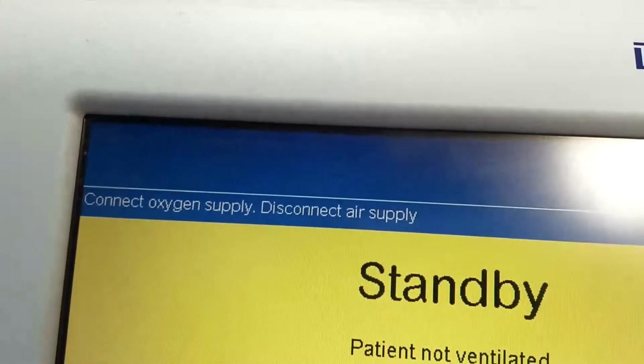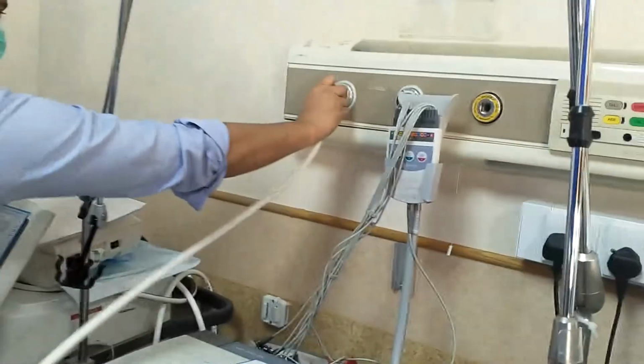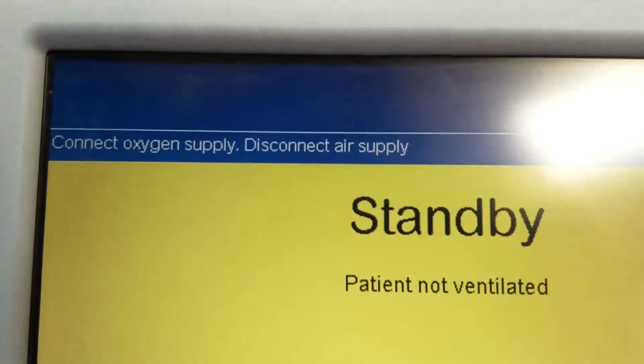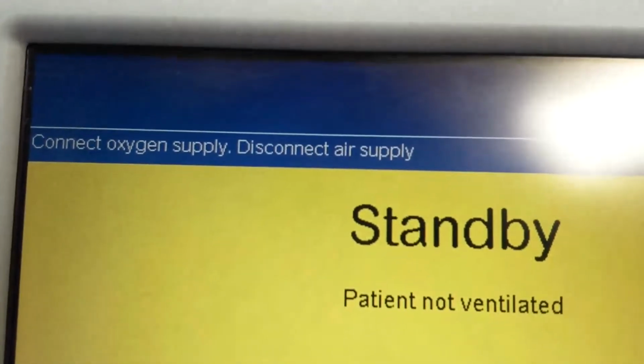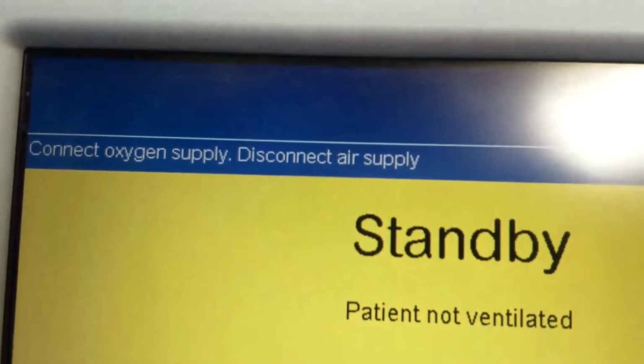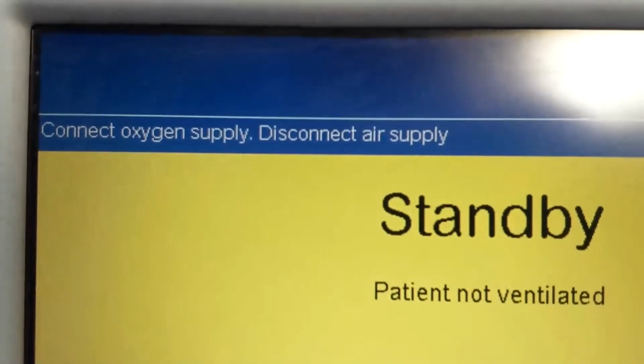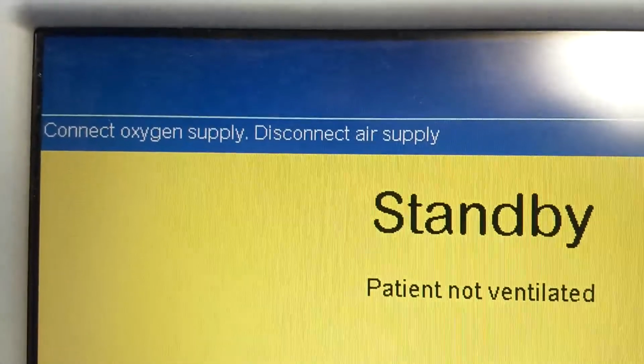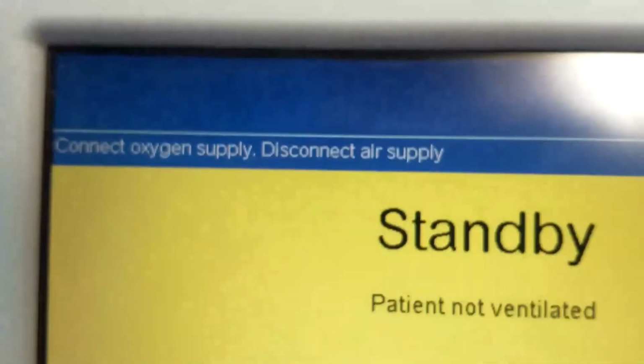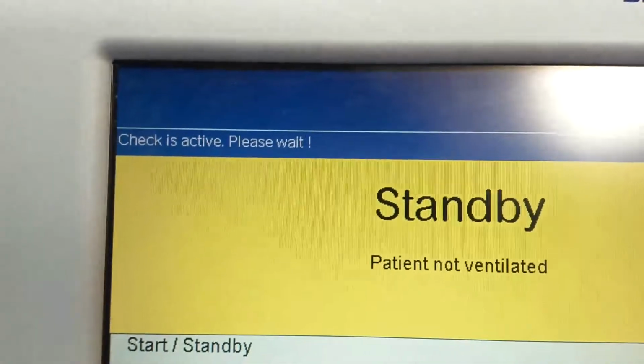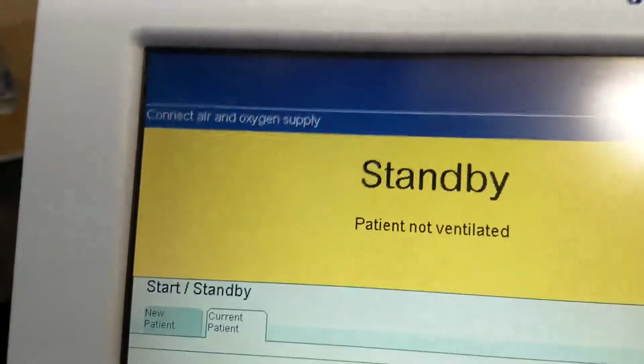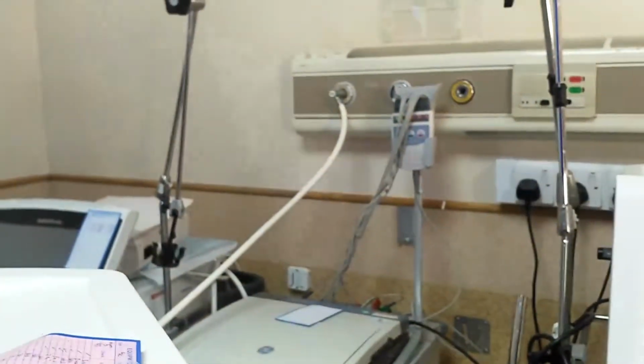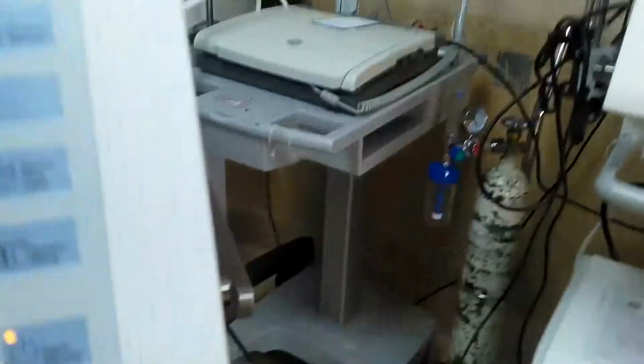Now it says connect the oxygen supply and disconnect the air supply. For disconnecting, we will turn off the compressor. It's waiting for the response. It takes a little time to understand that we have connected the oxygen supply and removed the air supply. Okay, it has understood that we have removed the air supply. Now it says connect the air and oxygen supply, and the oxygen supply we have already connected. For air, just turn on the compressor. Okay.